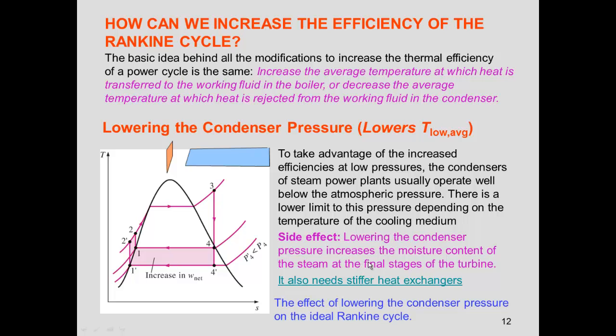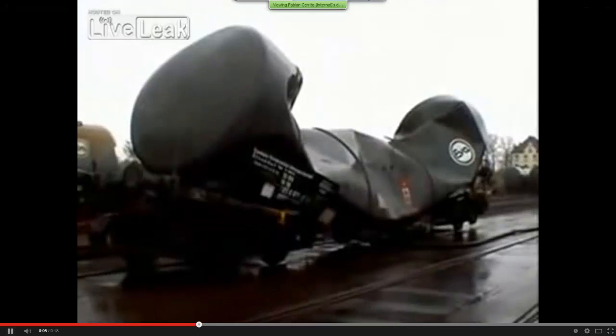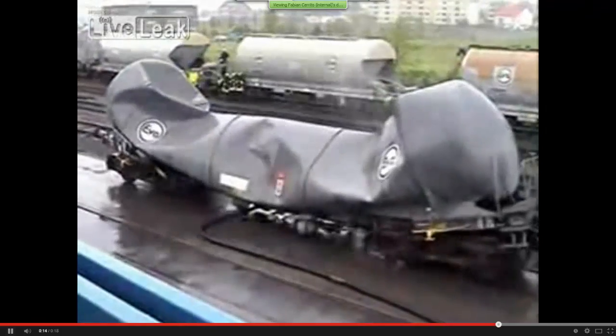However, there are side effects. Lowering the condenser pressure increases the moisture content at the turbine exit — moving from state 4 to 4 prime — which causes corrosion. It also requires stiffer heat exchangers, since the lower pressure creates a larger pressure difference with the ambient. This pressure difference can cause structural collapse, as illustrated by the video showing a vessel collapsing due to a vacuum-like condition.